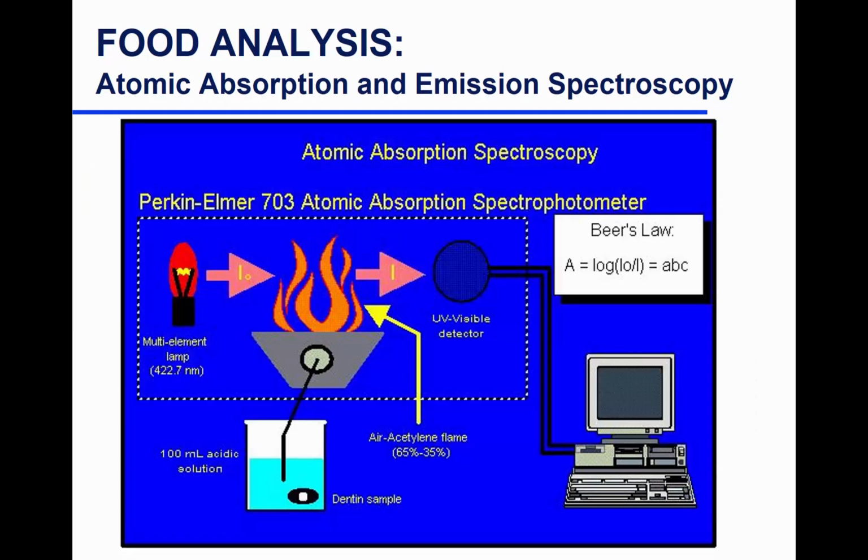Again, here's a general principle where you have your sample, the tubing that sucks the sample into the nebulizer. The nebulizer converts the liquid into a mist and puts it into the flame. And in the flame, you break the bond.